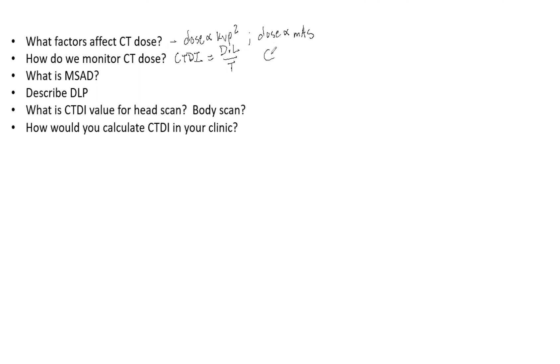So we also have CTDI weighted. That's what this W stands for. And that is one third the CTDI of the center, and that is added to two thirds CTDI of the periphery.